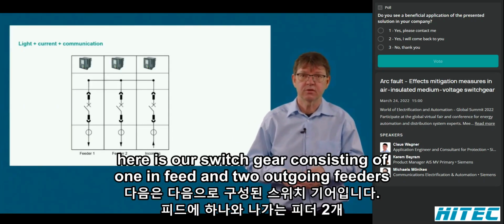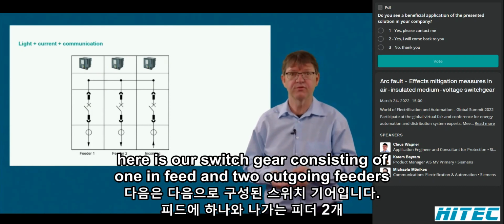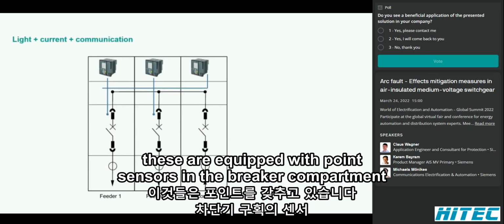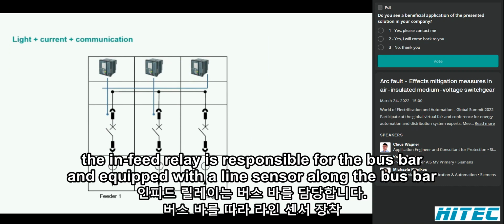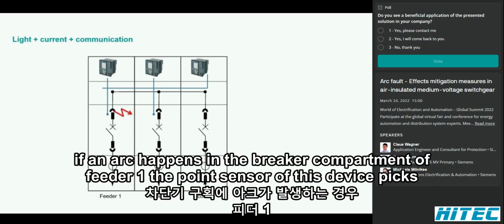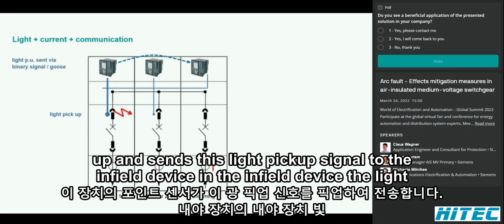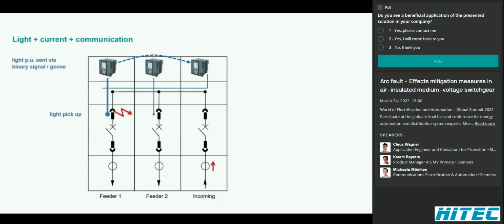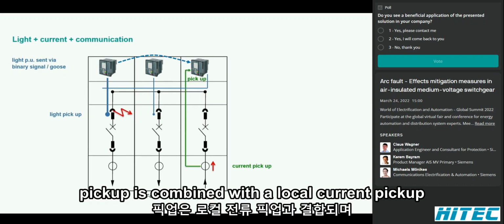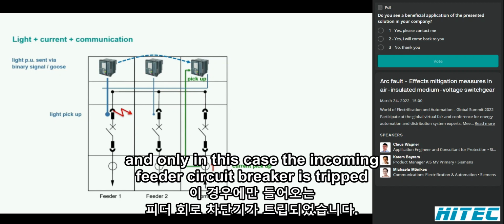Here's our switchgear consisting of 1 in-feed and 2 outgoing feeders. These are equipped with point sensors in the breaker compartment. The in-feed relay is responsible for the busbar and equipped with a line sensor along the busbar. If an arc happens in the breaker compartment of feeder 1, the point sensor of this device picks up and sends this light pickup signal to the in-feed device. In the in-feed device, the light pickup is combined with a local current pickup, and only in this case the incoming feeder circuit breaker is tripped.